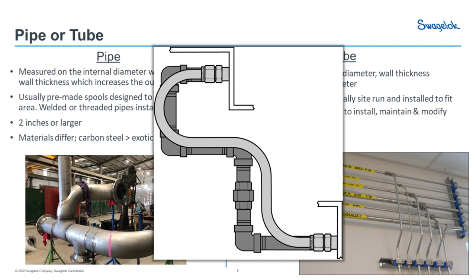Carbon steel is very common in piping but can range to some exotics like Alloy 625 or Hastelloy for more aggressive medias or environments. Tube is typically stainless steel but can also range into fairly interesting exotics — titanium, 6Mo, 2507, and some of the more expensive steels. You can see the difference in installation between pipe and tube. The pipe has about 10 additional connections over and above the tubing, and it's all threaded. The way the tube fitting works, there's no torque when the rear nut is pulled up — you just slide the tube in, tighten the two tube fitting connections while holding a backup wrench on the threaded connection, and it's installed. The piping you've got to orient and hope there are no leaks created. The installation difference is massive from a time perspective and a potential leakage perspective.